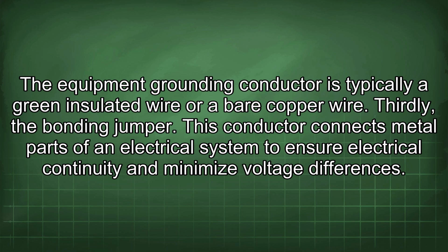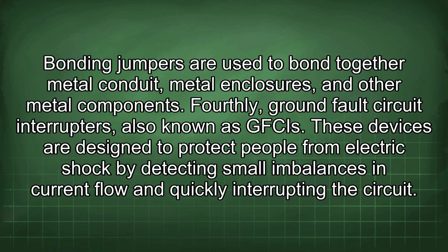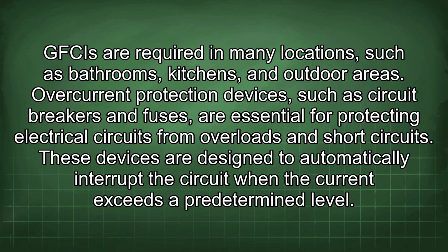Thirdly, the bonding jumper. This conductor connects metal parts of an electrical system to ensure electrical continuity and minimize voltage differences. Bonding jumpers are used to bond together metal conduit, metal enclosures, and other metal components. Fourthly, ground fault circuit interrupters, also known as GFCIs. These devices are designed to protect people from electric shock by detecting small imbalances in current flow and quickly interrupting the circuit. GFCIs are required in many locations, such as bathrooms, kitchens, and outdoor areas.